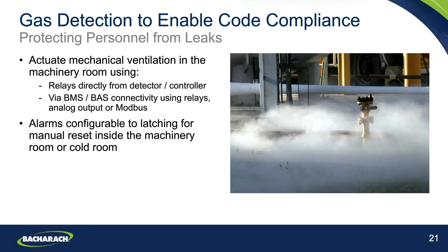Of course, we also need to be ensuring that we're actuating mechanical ventilation in the machinery room. This again can be done using relays directly from the gas detector or from a gas detection controller. But this, of course, can be driven by a building management system or front-end control system. And in order to do that, you want to be looking for connectivity from your gas detection system, either via relays, via an analog output, via a Modbus connection, some way of actually presenting that alarm status into the building management system in order to actuate those additional measures.